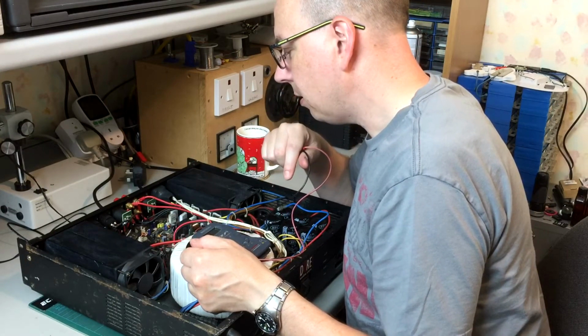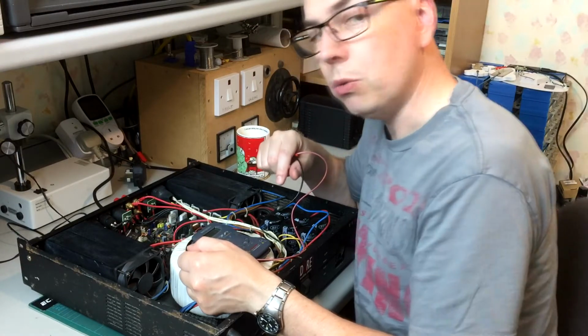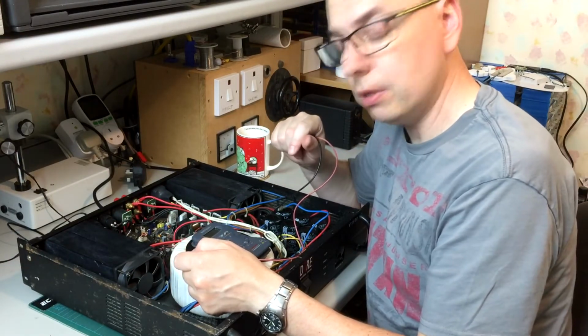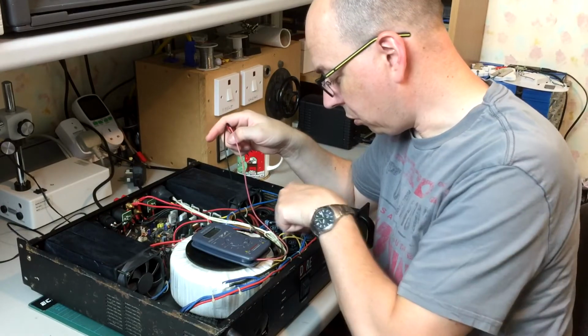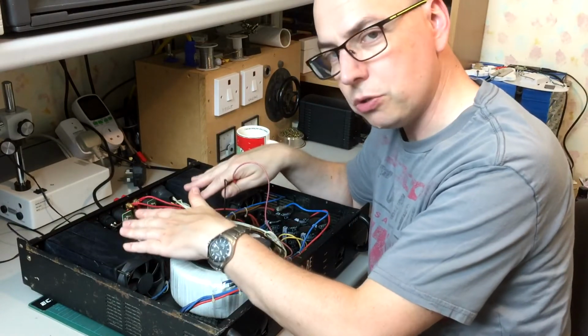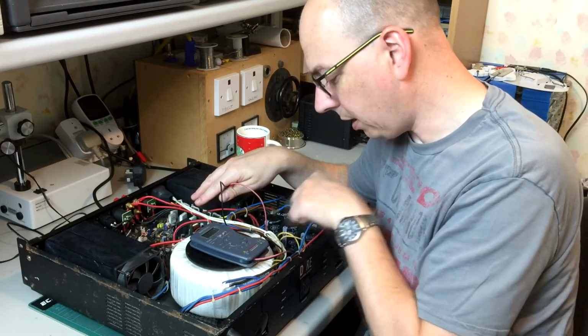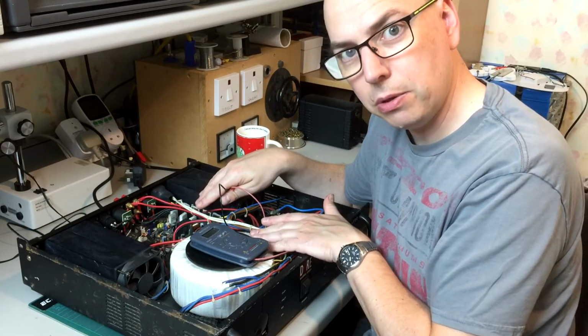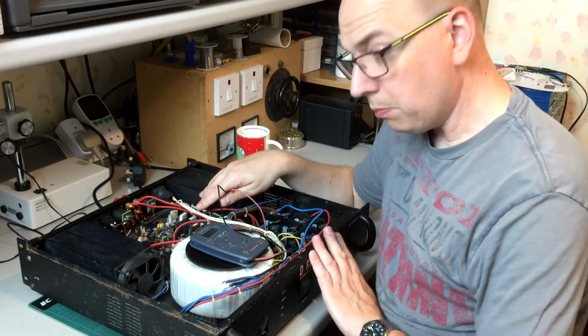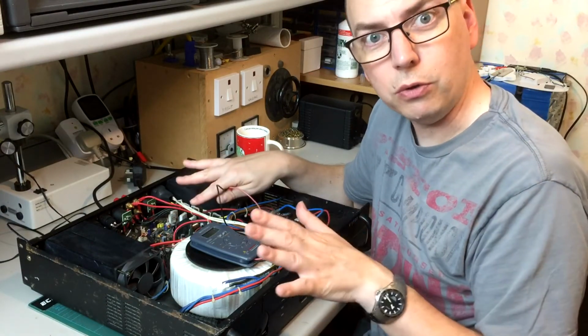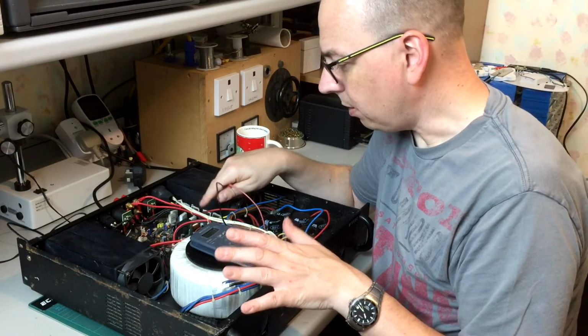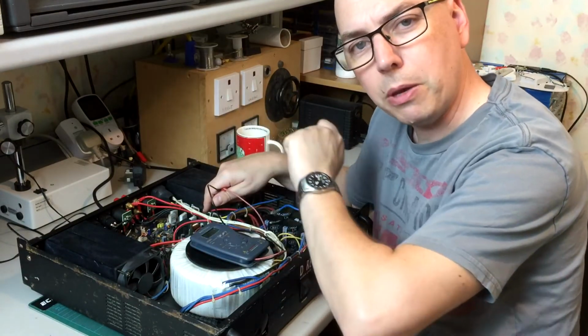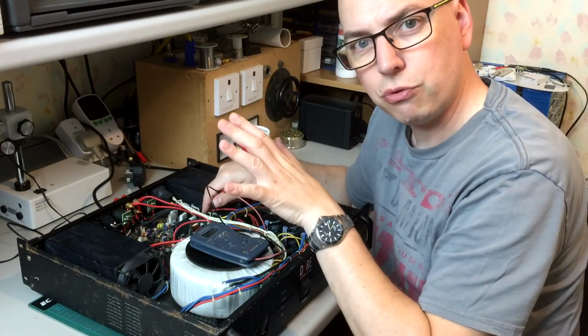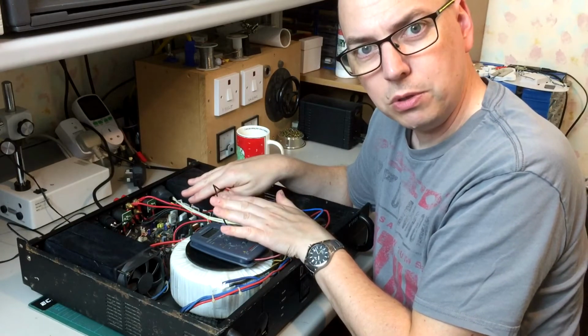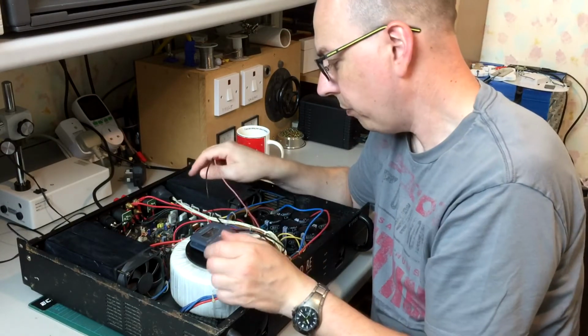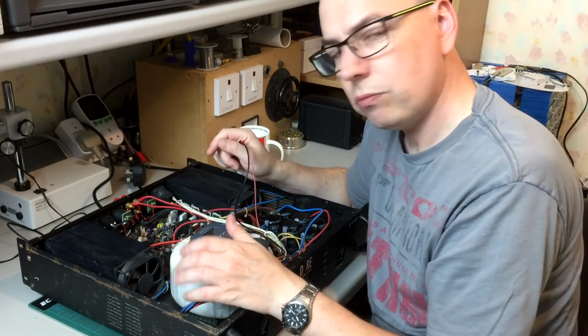Given that's the case, normally at this point I'll connect the bench supply up. The low voltage circuits, maybe the fan circuits and protection circuits, probably run on the 22 volt AC winding of this transformer. So if we power that up, we should see the lights come on. Maybe the protect mode will stay on because there's no high voltage rails present. Then we can bring the high voltage rails up on the power supply, see if there's any excessive current draw, any DC offsets on the output, any weird stuff going on at all. I think that's going to be the next stage.